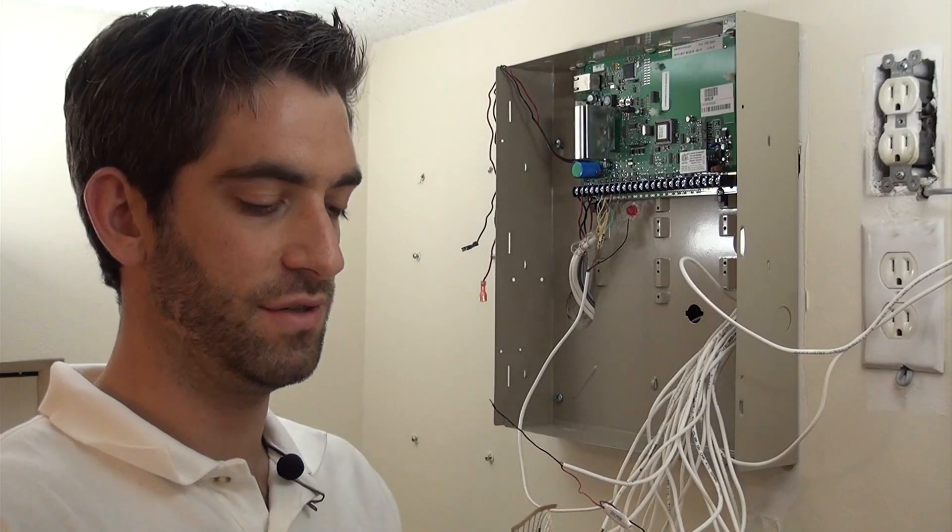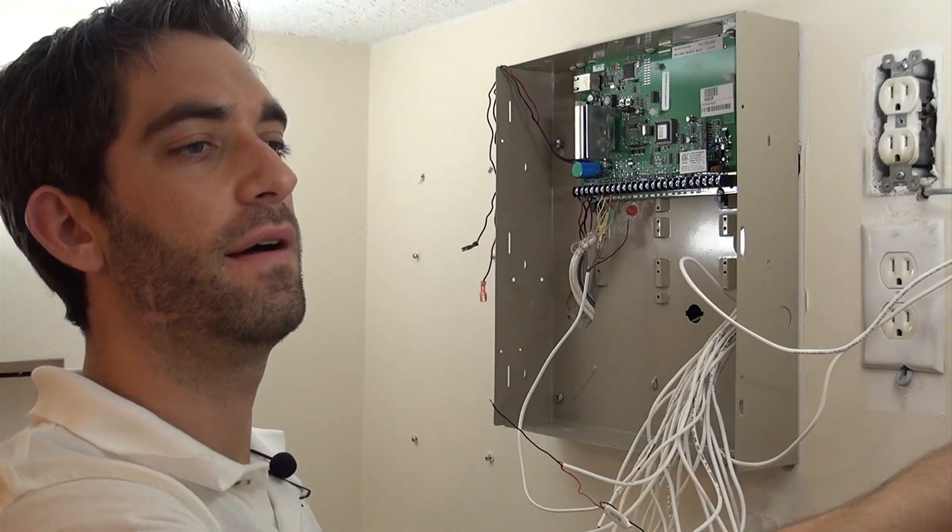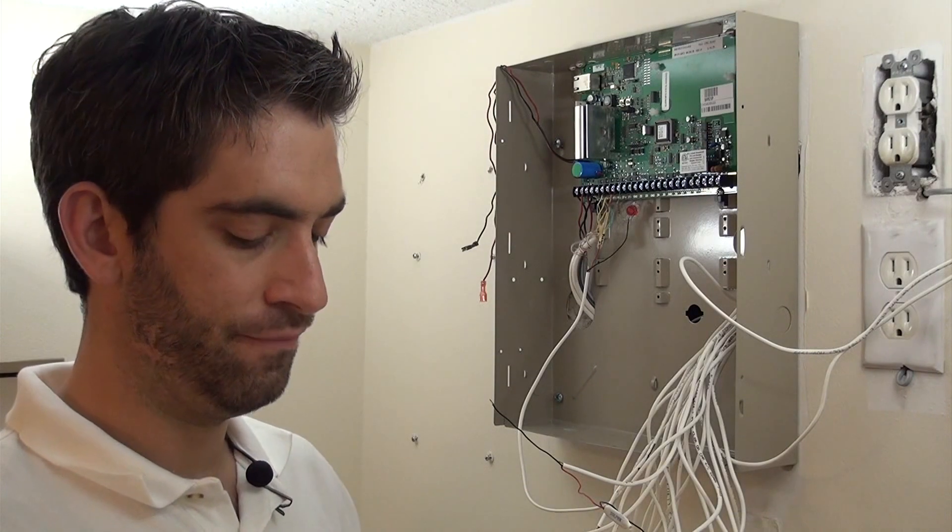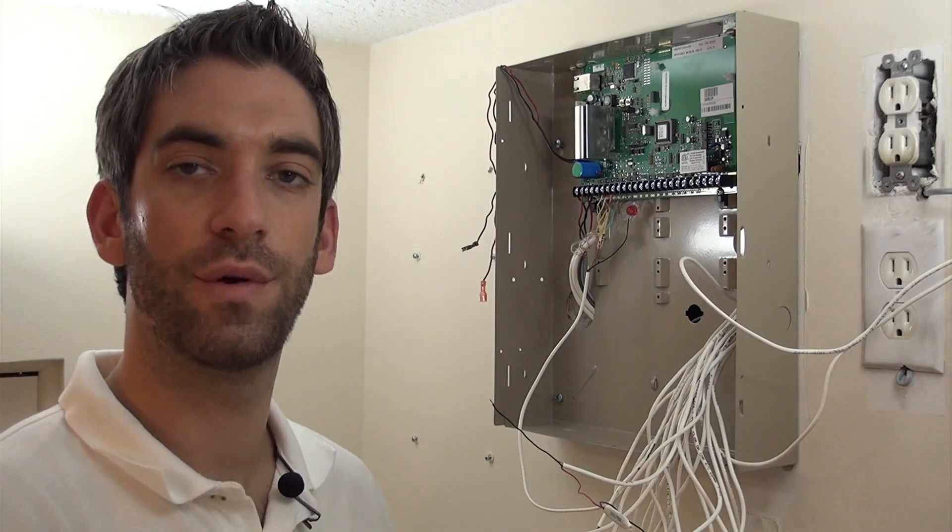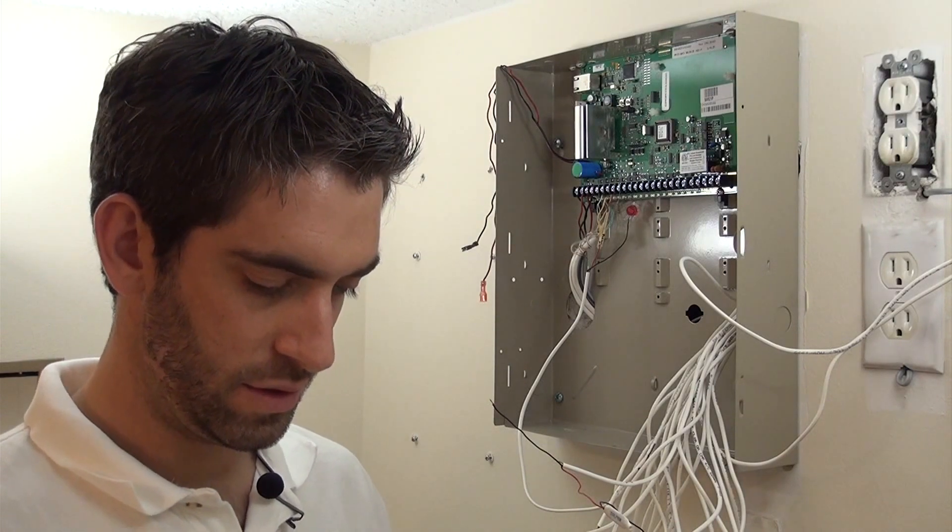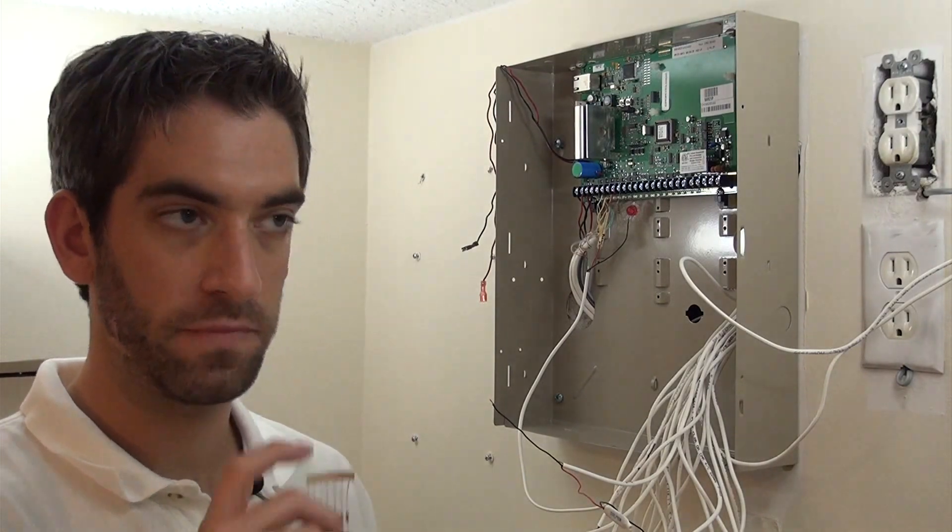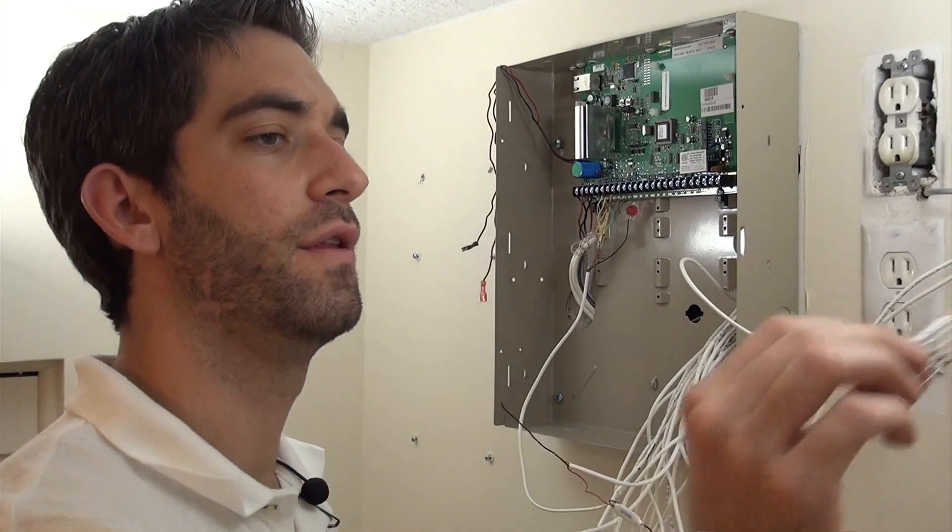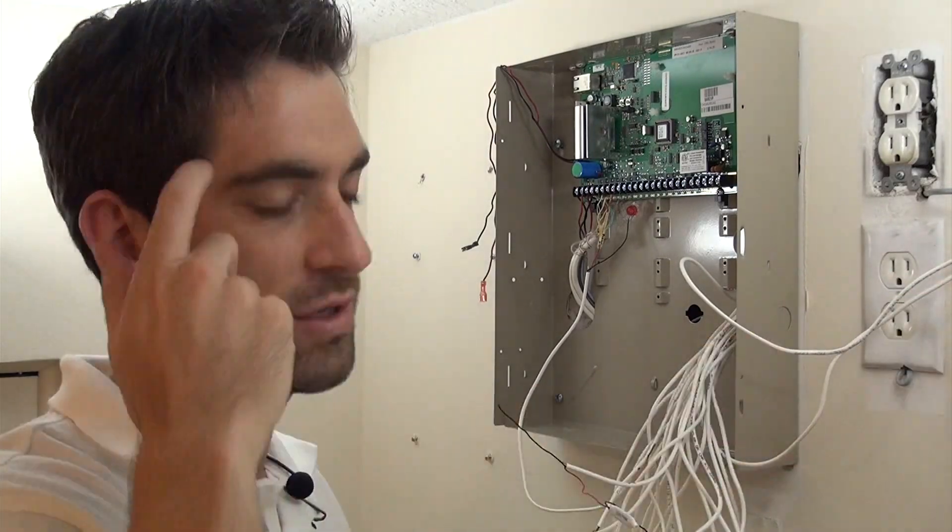So we've got our two sets of resistors here, and we've got our legend here to show us which is which. Important thing to note when you're doing your zone doubling is the 3Ks, the ones with orange, are going to go for the low side of the zone or the lower number of the zone, and the other ones for the higher number.